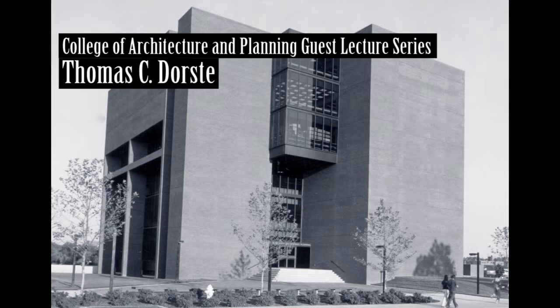The next building, and I'm still talking variable volume, was the National Retail Hardware Association, which is a smaller building, but still about 40,000 feet. And we carried the thing one step further. The entire center section is variable volume. The perimeter is hot water radiation controlled by an outdoor thermostat, so that there's no control on the interior in terms of interior changeable thermostats for that perimeter heat.